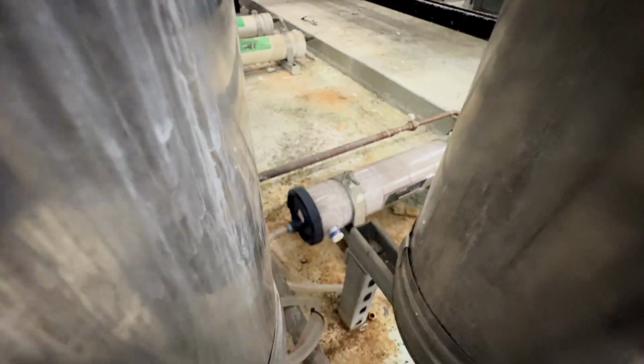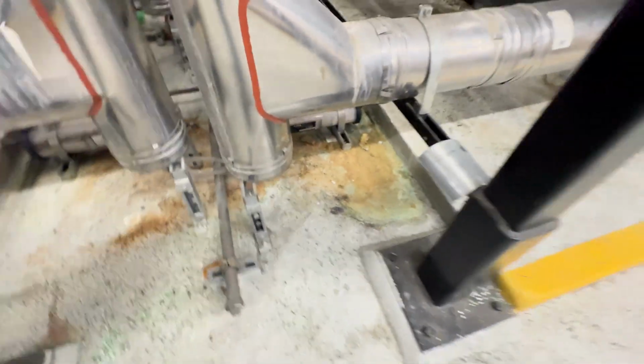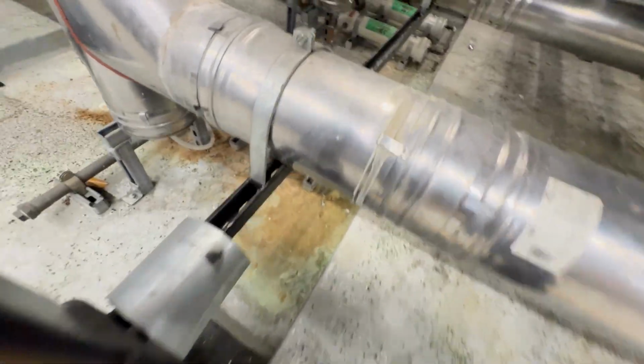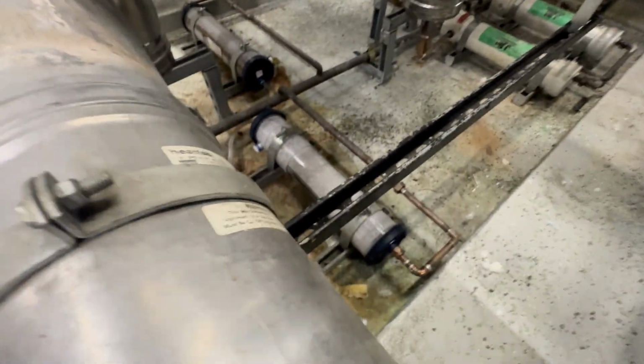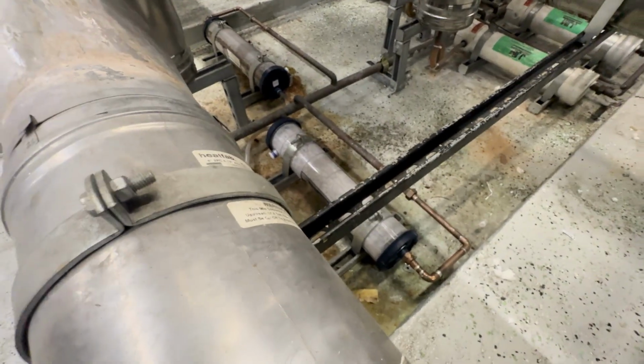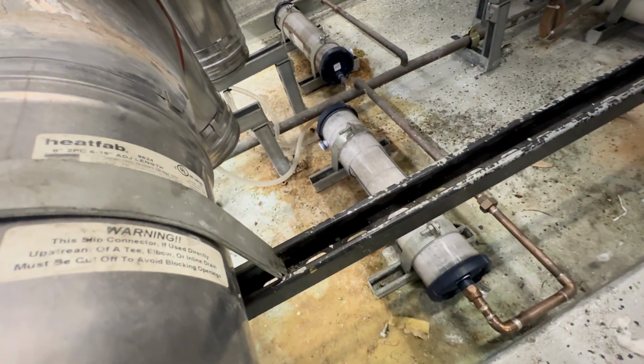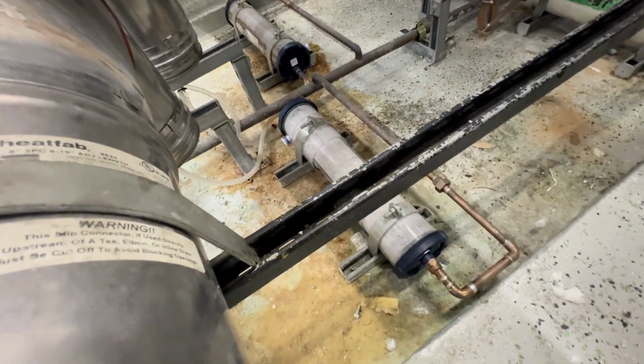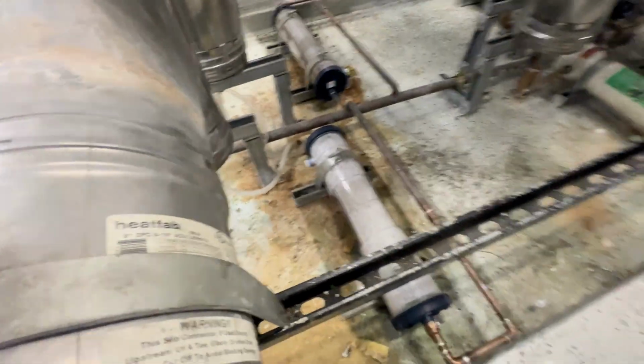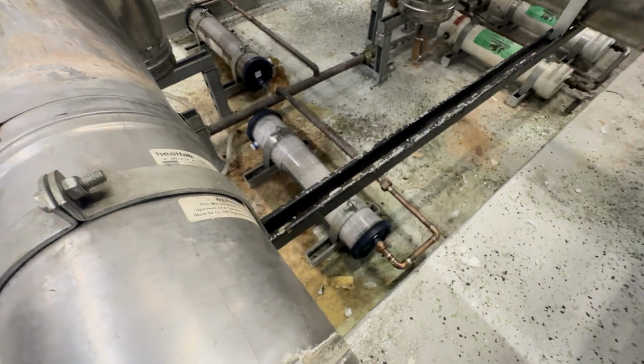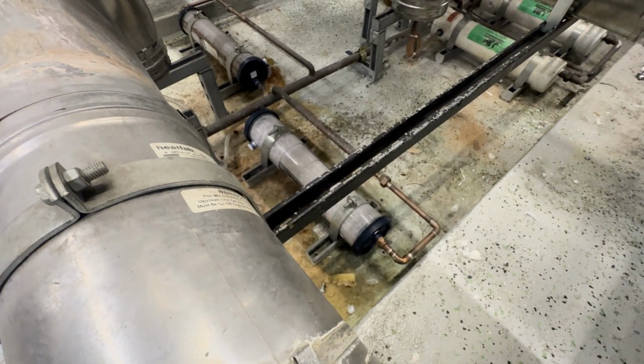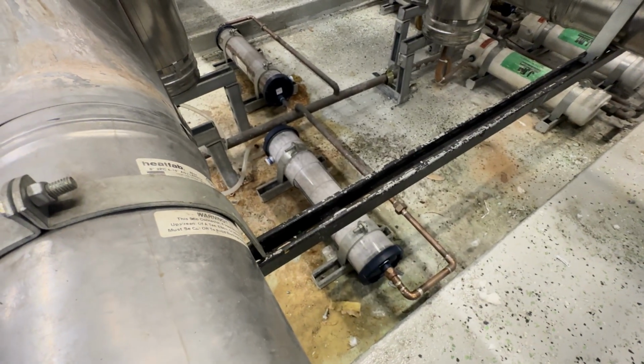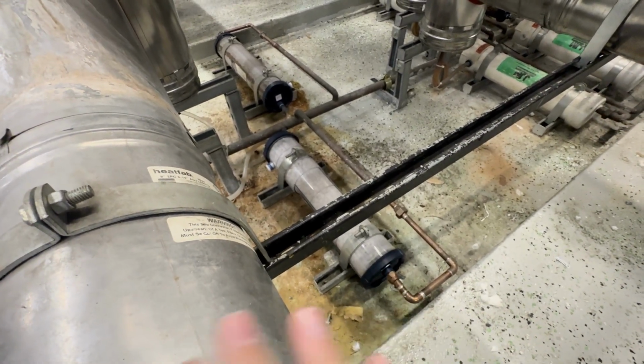After you finish testing all your safety controls, the next thing you're going to want to check out is your condensate drain system for the flue gas. We come over here. This little container has a little piece of plastic tubing that connects to it, goes through and then drains into a floor drain. So the purpose of this container is it's full of acid neutralizing pebbles. That flue gas condensate is pretty acidic, so it flows through these pebbles, it neutralizes it, and then it allows it to drain into the floor drain.